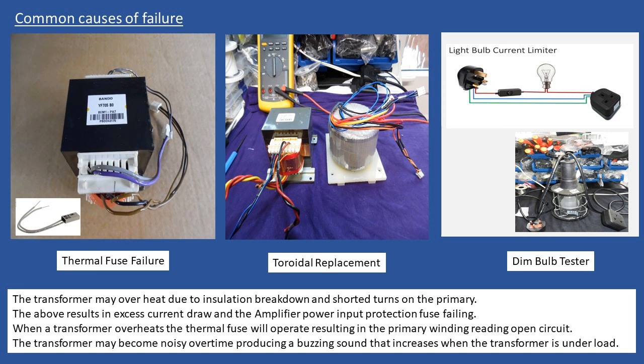So this is common where maybe it's just an amplifier, maybe not with a startup circuit, you put power on and it just doesn't power. There's no indication whatsoever. Then you get into it and you check through, and you realize, yeah, there's definitely 230 or 115 volts on the primary of the transformer. Then you check the voltage on the secondaries and there's no voltage at all. So isolate it from the mains power, and then when you put your multimeter onto resistance, you check it and it's open circuit. What has happened here is that the transformer at some point in time has gone above the thermal protection limit of that fuse. And these fuses are embedded into the windings of the transformer.